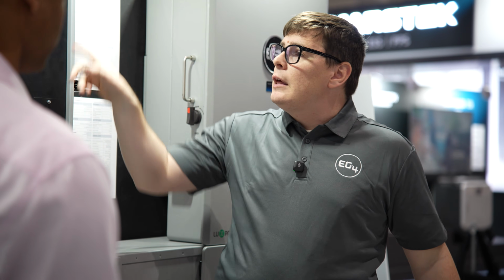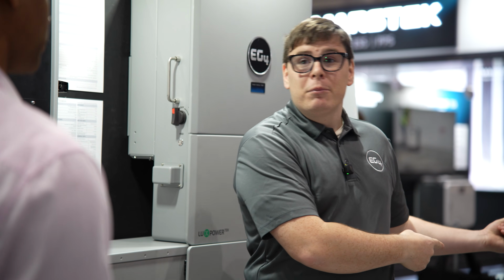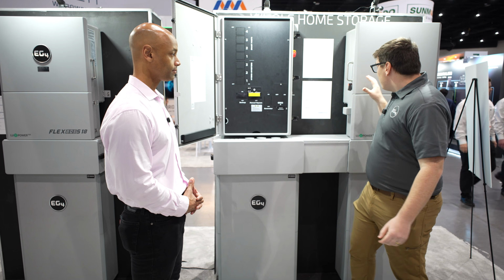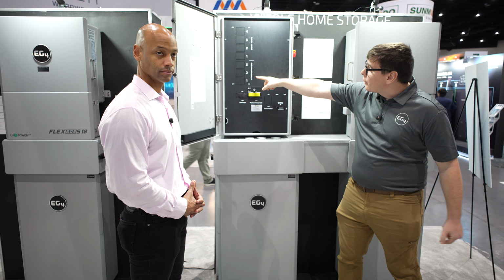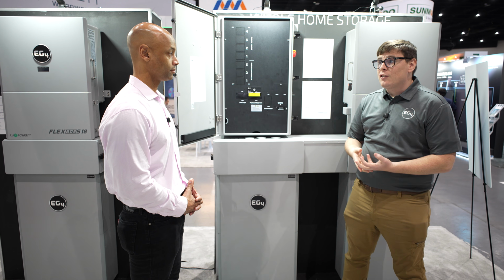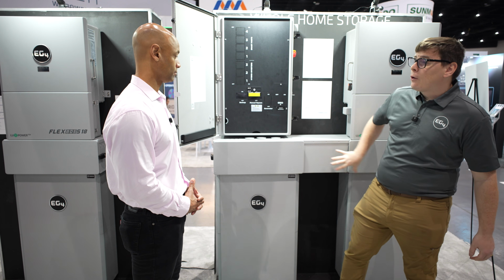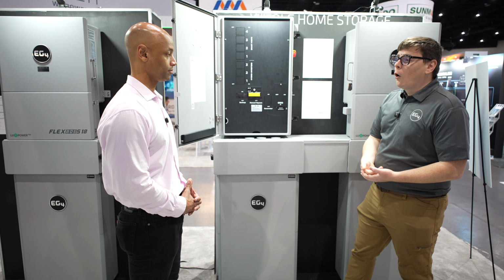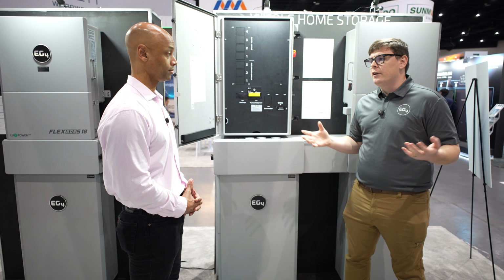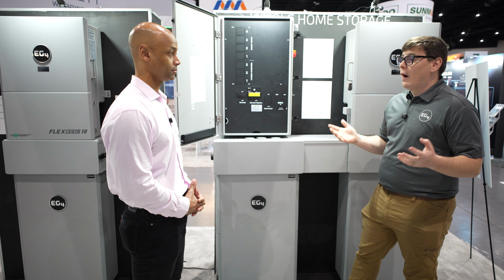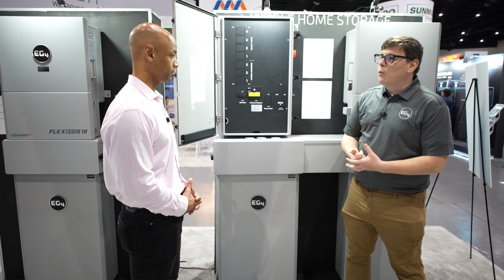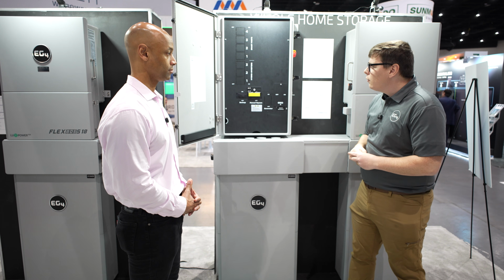It also is the input-output manager for the house. All these inverters used to have a sending wire from the grid and a return wire to the house. If you use a 200 amp inverter, for every foot you move away from the meter, Joe, this might be surprising, it's $60 a foot to run 3-aught wire from the meter to the inverter and back to the meter. Well, remember how we've got this device set up with a single wire connection at 6 gauge or 4 gauge, so maximum you're spending $6 a foot instead of $60 to move your batteries wherever you want to put them, as a homeowner or as an installer serving your client. I've got people who want the stuff 50 feet away from the meter, 100 feet away from the meter. That adds up to $6,000, $7,000 of wiring. People can't afford that. So this solves that problem in a way that I think some of the other hub inverters did. We brought that solution out on the hybrid side.